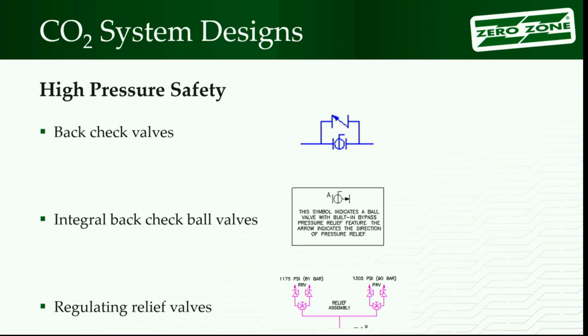So, high pressure safety. Depending on the system, some systems will have things to help avoid getting a high pressure in a segment of your piping, possibly a vessel, whatever. One of the ways is a back check valve. If I close off sections of my piping, it's isolated, I did it inadvertently, and the pressure starts building up, in a lot of cases there'll be a check valve around that isolation valve. That check valve will open up and bleed the pressure down. So if I'm isolated and this pressure starts going up, it bleeds it into that line. We'll see on some of the drawings, if there's another isolation valve, there's another check valve. A lot of times that bleeds back, you follow the trail back to the receiver.